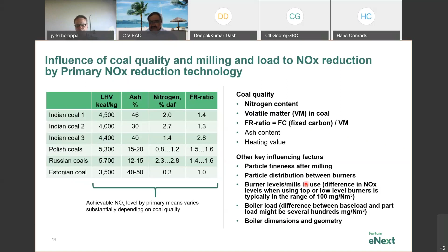What we typically see is that in India, boilers have overfiring systems called COFA, coupled OFAs. Most boilers do not have separate OFAs, SOFAs. A separate OFA means air supply is introduced a little further up in the boiler, not immediately above the topmost burner.